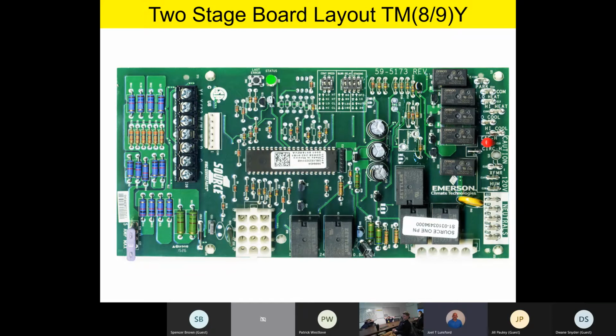And that's really some of the things I like about our Johnson Controls Champion furnace products in general, is the fact even if you're stuck with a single-stage thermostat, we can still give you some staging function. And so unlike our competitors, where if you just jumper W1 and W2, you have a 10-minute time delay between first and second stage, and that's all you get. Well, on our Champion products, if you have a 2-stage heating product or 2-stage furnace product on our Champion furnaces, we give you some staging capability by moving some dip switches.